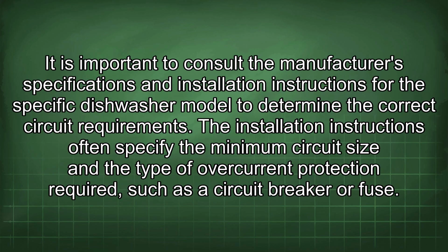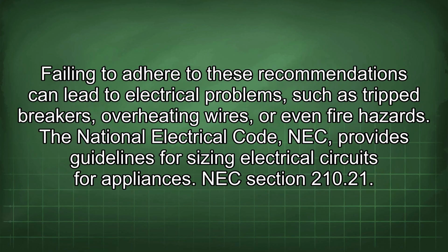It is important to consult the manufacturer's specifications and installation instructions for the specific dishwasher model to determine the correct circuit requirements. The installation instructions often specify the minimum circuit size and the type of overcurrent protection required, such as a circuit breaker or fuse. Failing to adhere to these recommendations can lead to electrical problems such as tripped breakers, overheating wires, or even fire hazards. The National Electrical Code (NEC) provides guidelines for sizing electrical circuits for appliances.